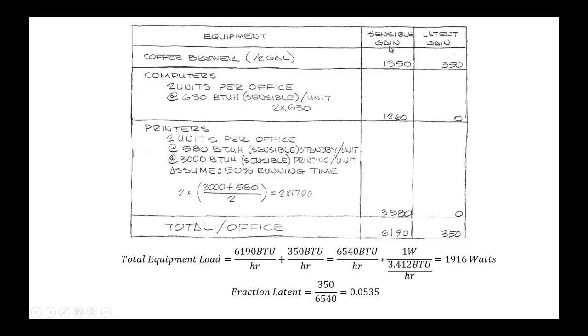So if you look this up, this is the sensible heat gain and the latent heat gain. The sensible heat gain for the printers was basically using the assumption that in standby, it's 580 BTUs per hour, and printing it's 3,000 BTUs per hour. We're just going to assume a 50% run time, so you take an average.